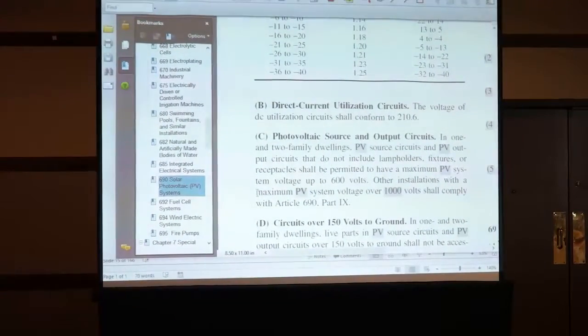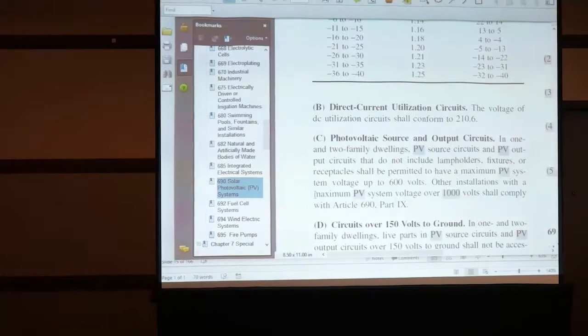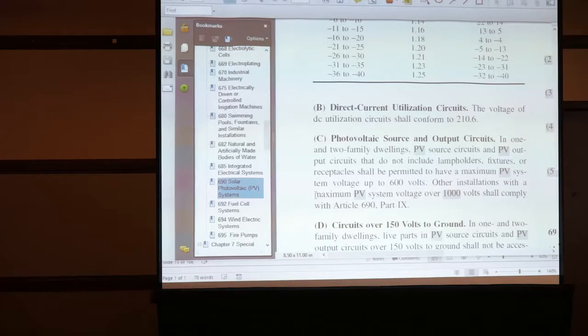Okay, so here we are, 690.7. It's in the preamble. Now, some of this has been cleaned up since then, but we'll just go with what it currently says. Let's see, that's for lowest expected ambient temperature. I think it's over here and keep on going down. Here we are. Source and output circuits. In 1 and 2 family dwellings, source and output circuits that do not include lamp holders, fixtures, or receptacles shall be permitted to have a maximum PV voltage of 600 volts, up to 600 volts. Other installations with a maximum PV system voltage over 1,000 volts shall comply with that.